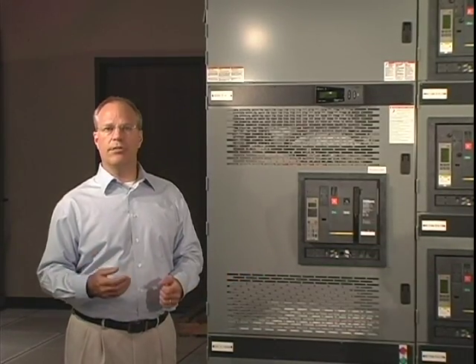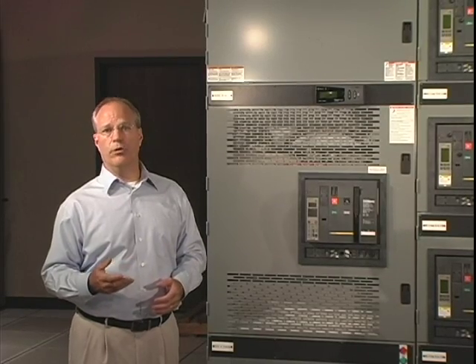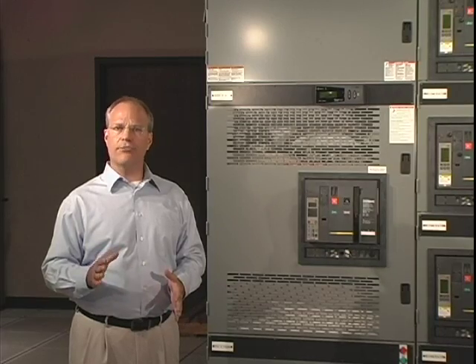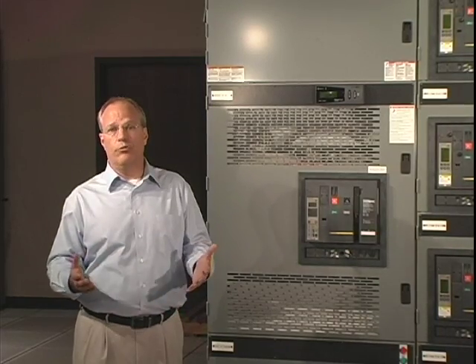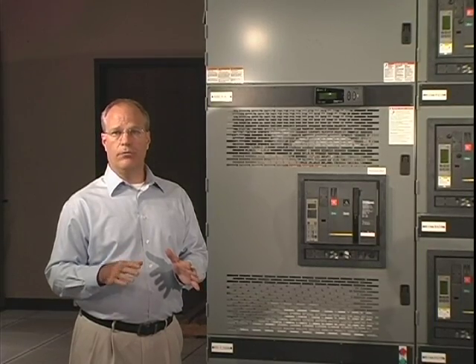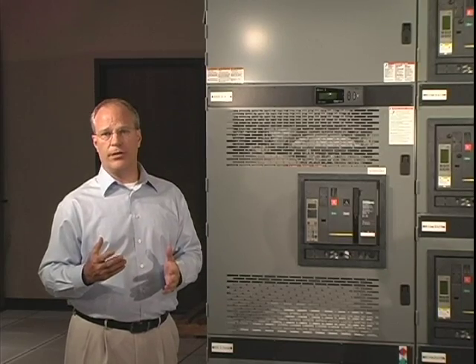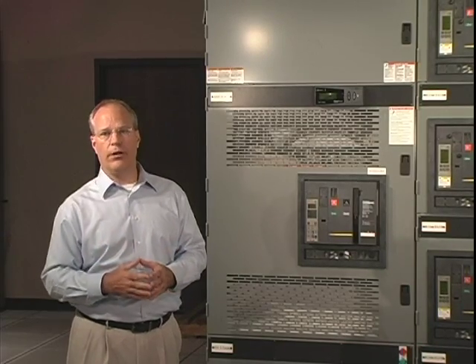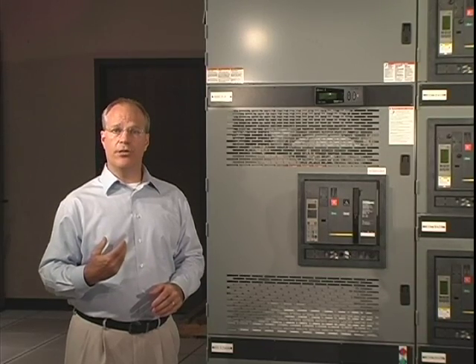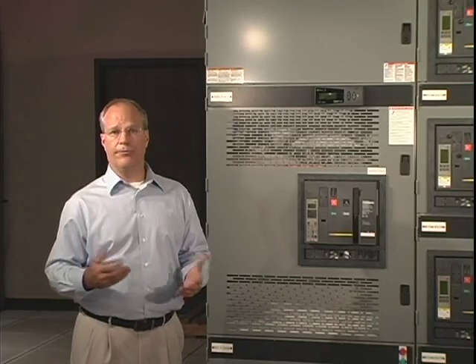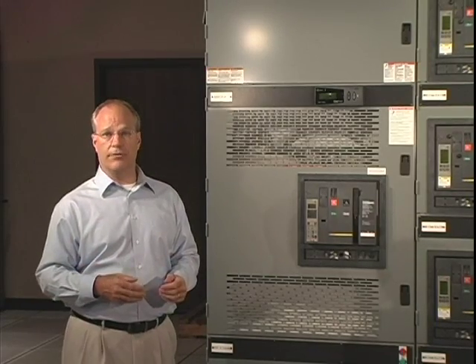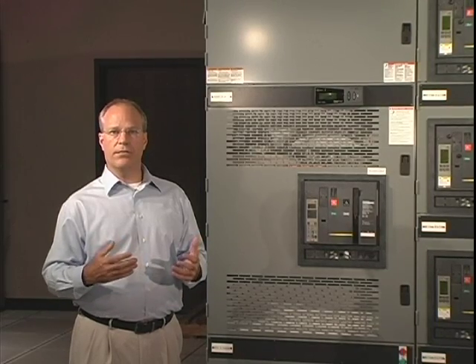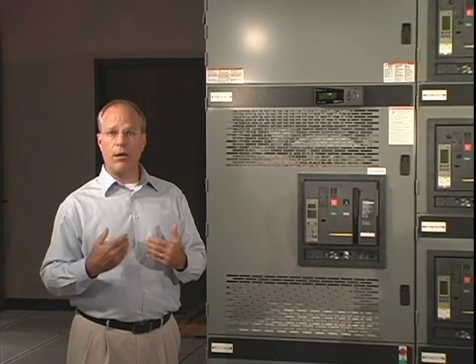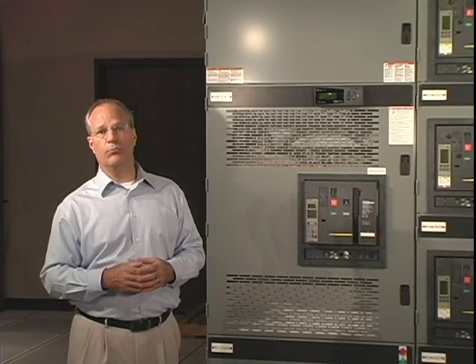No, they do not. Since the evolution of the insulated frame breaker design that was pioneered by Schneider Electric, the Masterpact series of breakers has proven to be very reliable and dependable over the life cycle of installed applications. Schneider Electric is proactively advising those customers that there is now a solution for consideration. The application of the breaker, duty cycle, and operating environment all come into consideration as to whether the facility would have a need or desire to upgrade these breakers. For example, if I'm the facility engineering manager or the facility maintenance manager who is responsible for the electrical distribution system within a medium-sized data center facility, and I have the responsibility of the system, I realize that's of utmost importance, then I would consider the upgrade and I would enhance my system with the communications capability.